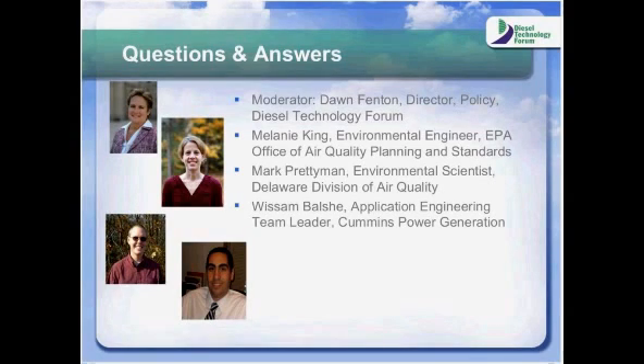Okay. I had one more thing I wanted to clarify when talking about thermal efficiencies. The thermal efficiencies of diesel gensets are better mainly for low range. A lot of the high horsepower gas gensets have comparable thermal efficiencies to diesel high horsepower engines. And the other thing regarding the starting time, or from the moment of accepting load and recovering to voltage and frequency, the 2-minute or 1-minute rule for gas really applies only to high horsepower. You can meet the 10-second rule with the small low-range gas generator sets. I know we sell up to 150 kilowatt gensets that can meet the 10-second rule. So this really applies more to commercial and large industrial applications. Okay, great. Thank you for that clarification.